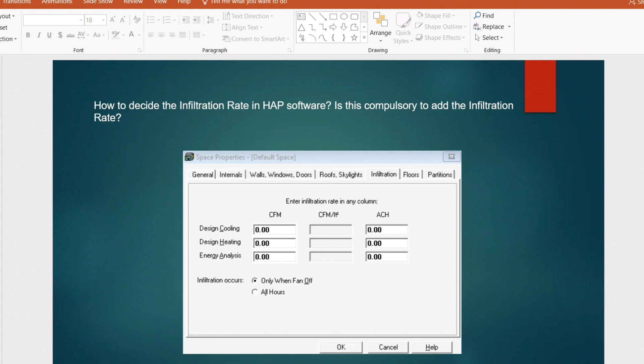The first question is: how to decide the infiltration rate in HAP software, and is it compulsory to add the infiltration rate? In HAP software, when it comes to spaces there will be one option for infiltration where you have to provide the infiltration value in air changes per hour. This is important because a high infiltration rate will give both sensible and latent cooling load in a very high amount.